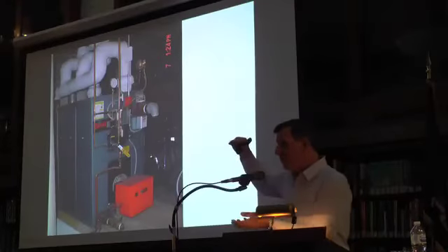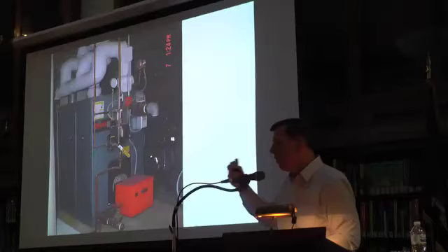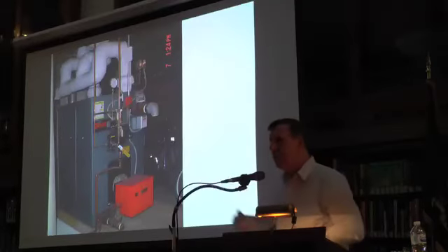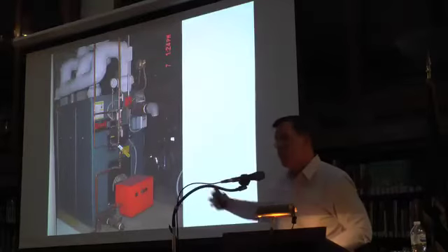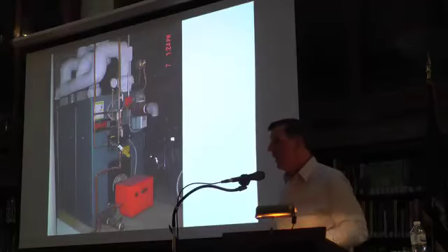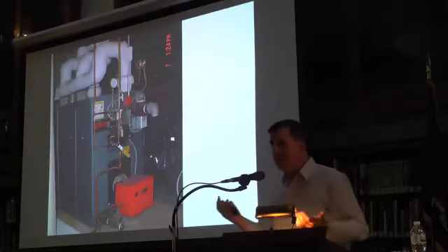So you wind up with this kind of a rubber sheet laying on the top that is the oil, and it causes very violent boiling inside, and you start to get what's called priming, and that's where water's shooting up into the system and out into the pipes. The boiler goes off on low water. A low water cutoff comes on to replenish the water, to keep the boiler running, and then all the stuff comes rushing back from the system, and now the boiler's flooded. So somebody's got to go and drain it, and that involves sometimes chemicals that are being thrown away. It involves hot water that's being thrown away, and it just keeps increasing the fuel bill.